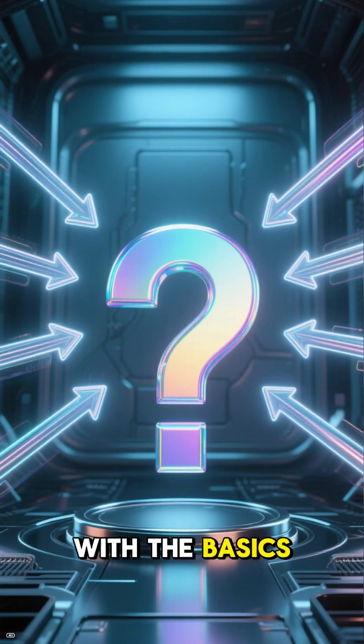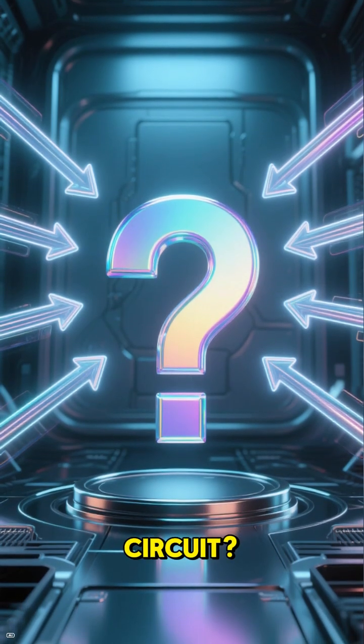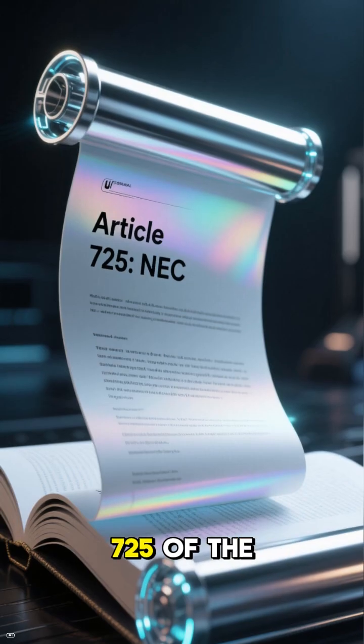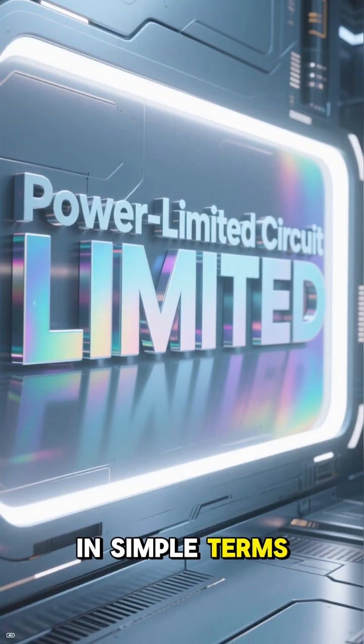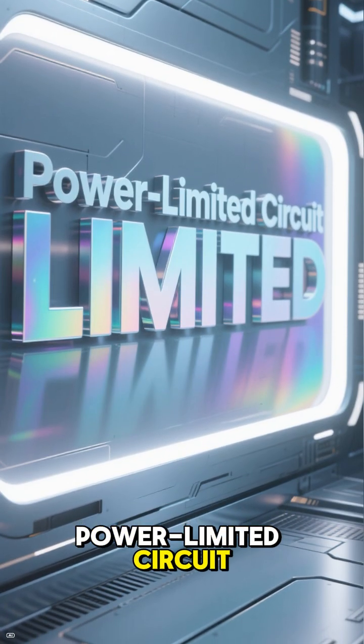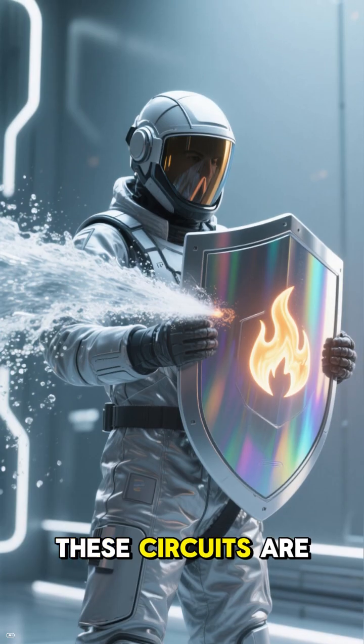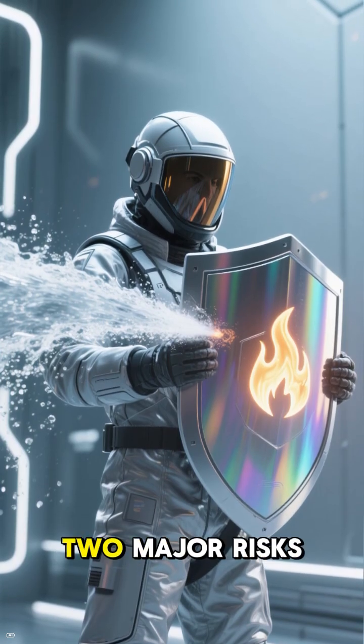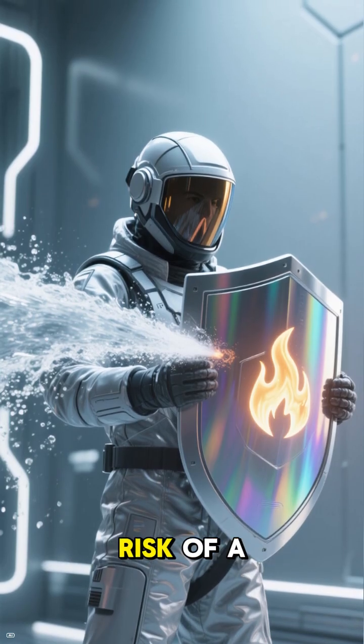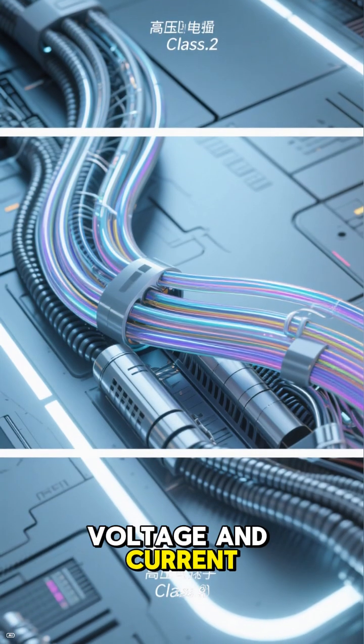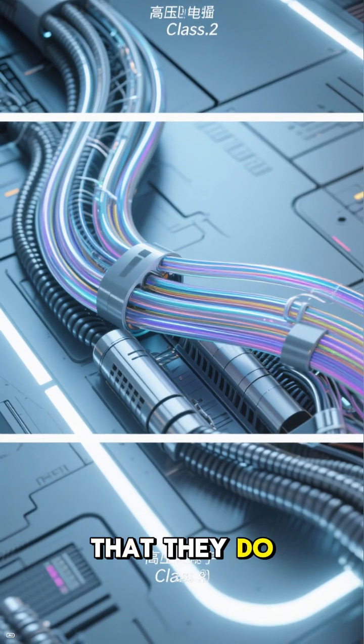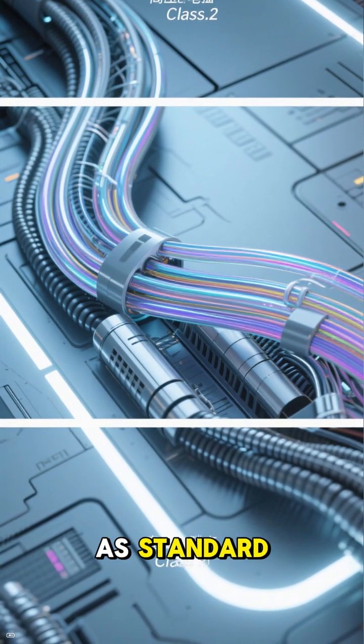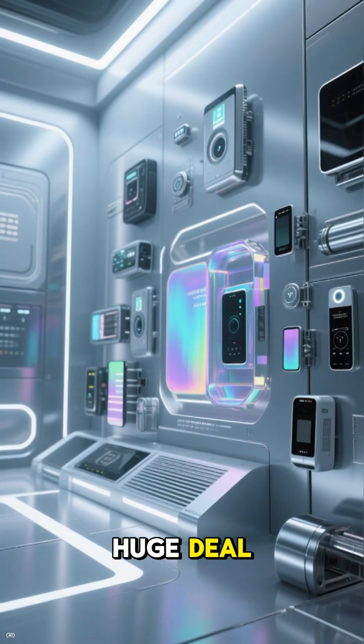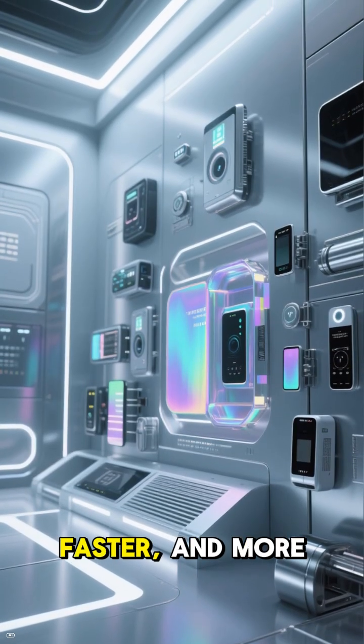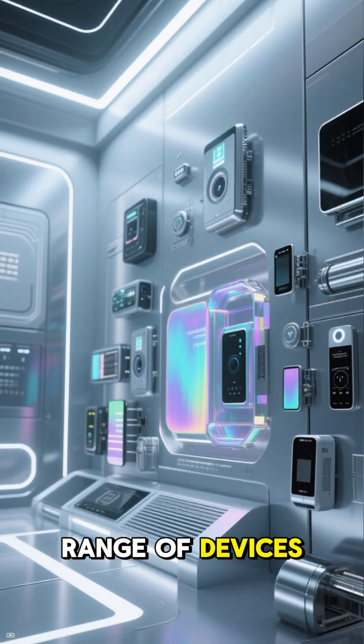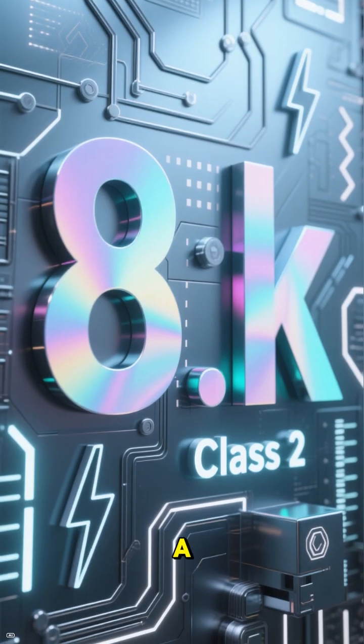So, let's start with the basics. What exactly is a Class 2 circuit? The official definition comes from Article 725 of the NEC. In simple terms, a Class 2 circuit is a power-limited circuit. The key word here is limited. These circuits are specifically designed from the ground up to minimize two major risks, the risk of electrical shock and the risk of a fire. By strictly limiting the voltage and current, the NEC deems these circuits safe enough that they don't require the same heavy-duty wiring methods as standard 120-volt power circuits. This is a huge deal, and it's what allows for simpler, faster, and more cost-effective installations for a whole range of devices. Let's get into the specific numbers that define a Class 2 circuit.